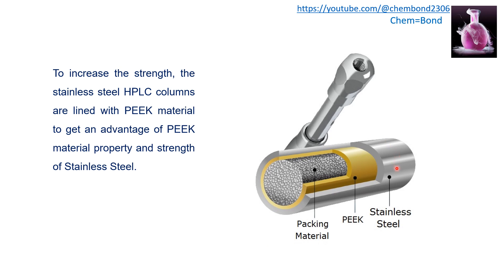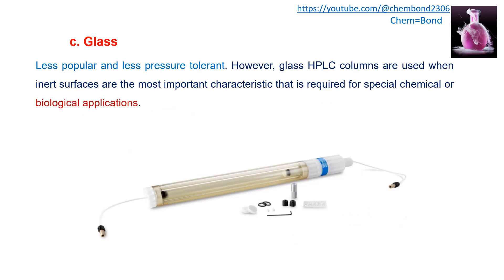Stainless steel provides mechanical strength and withstands high pressure, while PEEK offers chemical and mechanical resistance at high temperatures. To combine both advantages, stainless steel HPLC columns are lined with PEEK material, giving the benefits of PEEK's properties along with the strength of stainless steel in a single column. Glass columns are less popular and less pressure tolerant, but are used when inert surfaces are the most important characteristic required for special chemical or biological applications.